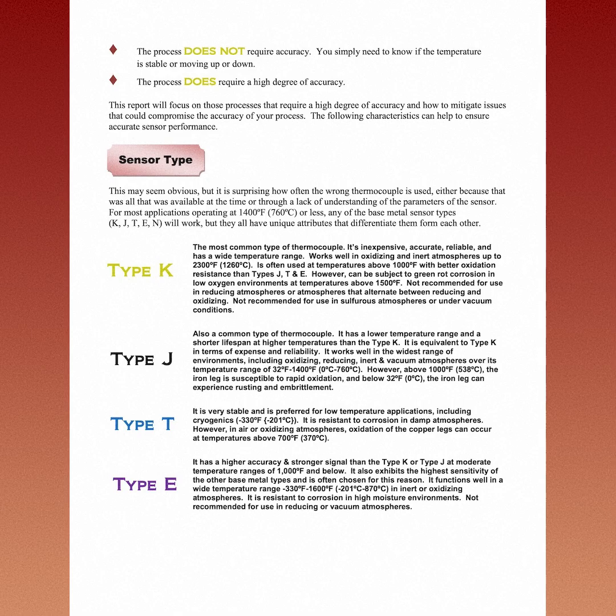It's inexpensive, accurate, reliable, and has a wide temperature range. Works well in oxidizing and inert atmospheres up to 2,300 degrees Fahrenheit or 1,260 degrees Celsius. Is often used at temperatures above 1,000 degrees Fahrenheit with better oxidation resistance than types J, T, and E. However, can be subject to green rot corrosion in low oxygen environments at temperatures above 1,500 degrees Fahrenheit. Not recommended for use in reducing atmospheres or atmospheres that alternate between reducing and oxidizing. Not recommended for use in sulfurous atmospheres or under vacuum conditions.